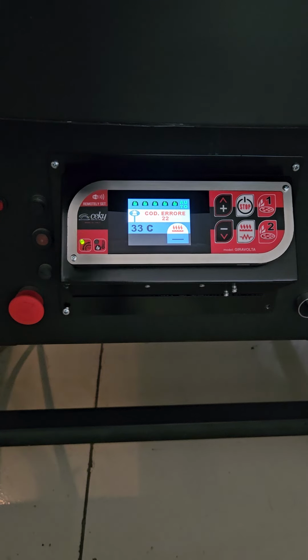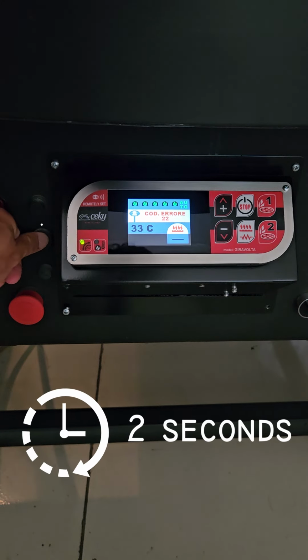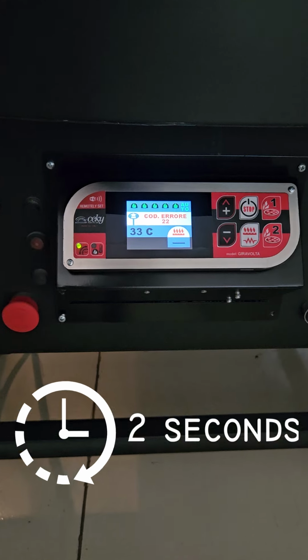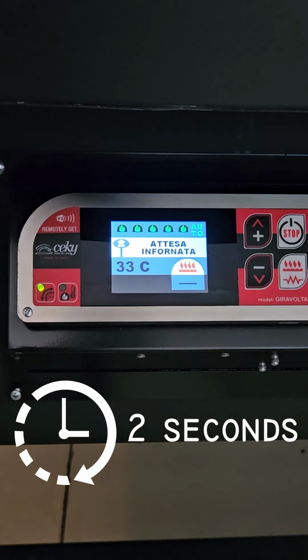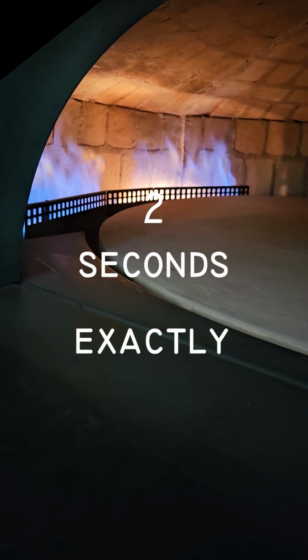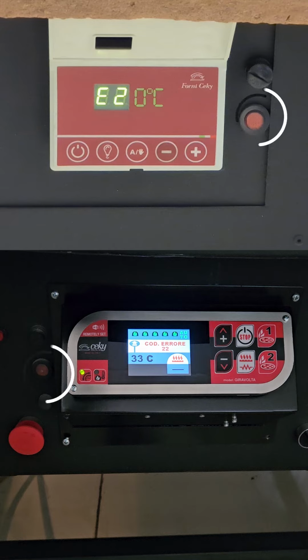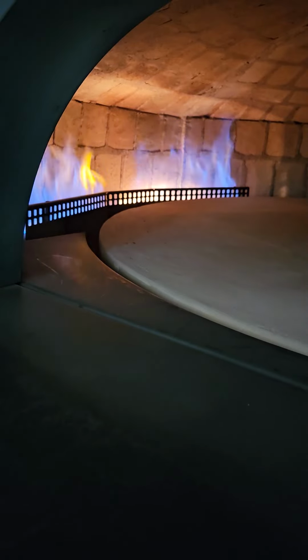To reset the E2 error and rearm the burner, simply press and hold the reset button for 2 seconds, then release it. It is crucial that the button is held for exactly 2 seconds. Holding it for 1 or 3 seconds will not reset the error. The reset button is the red button next to the console. Once reset, the error will clear, and the burner will restart the ignition process.